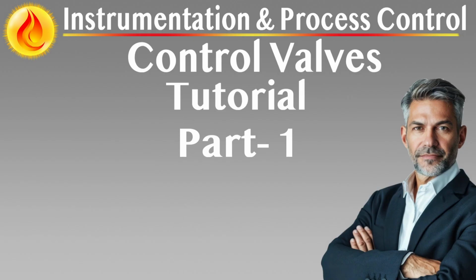Preferred nominal sizes for control valve bodies are DN 25, 40, 50, 80, 100, 150, 200, 250, 300, and above. Valve sizes below DN 25 require explicit principal approval.